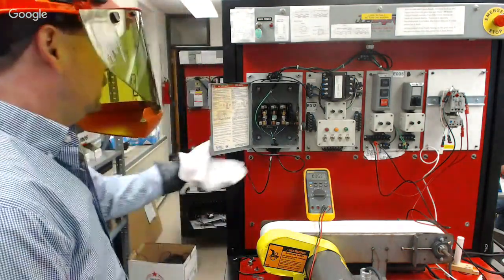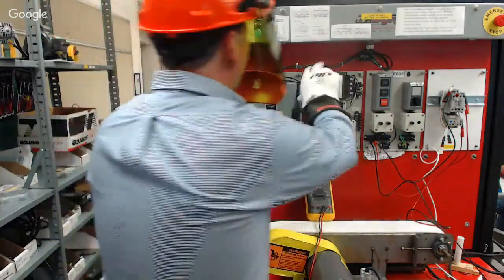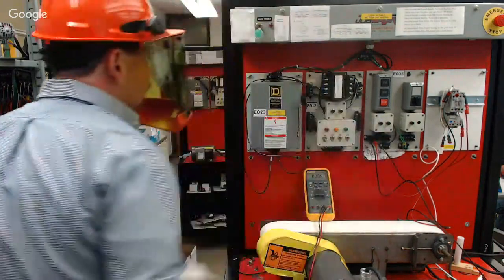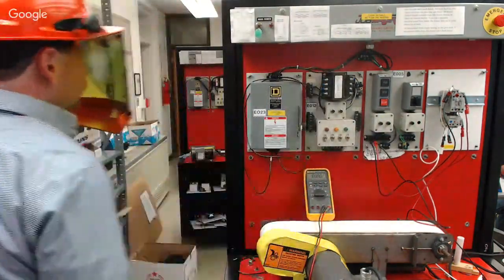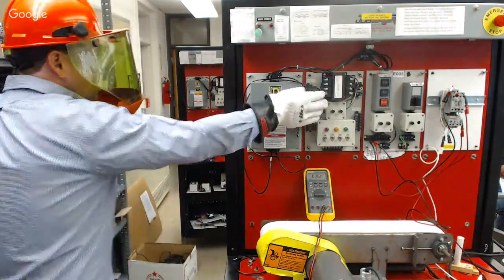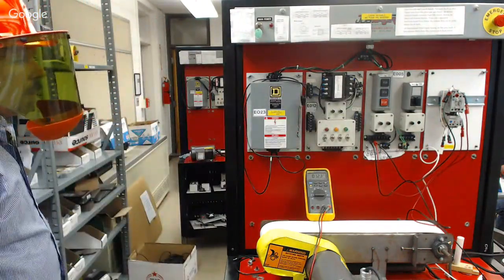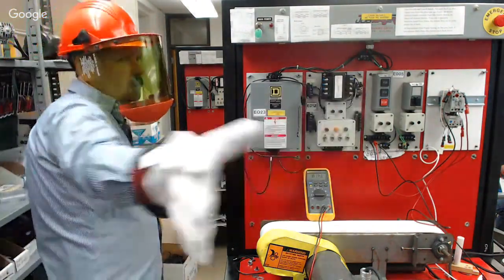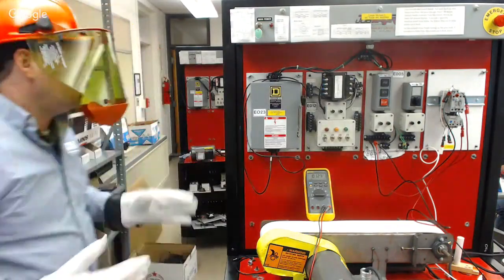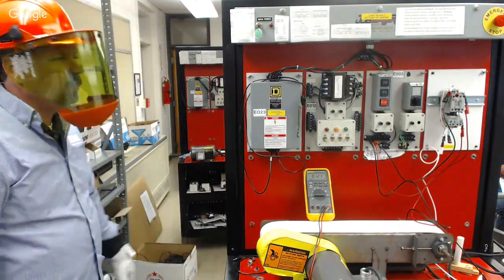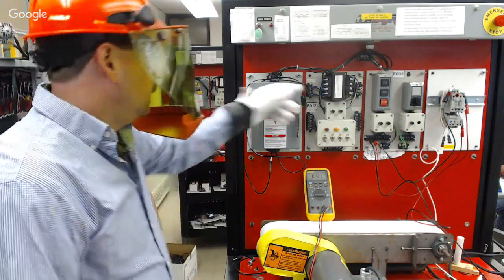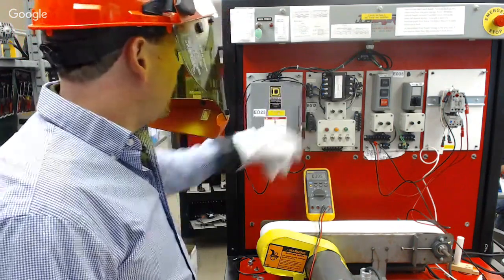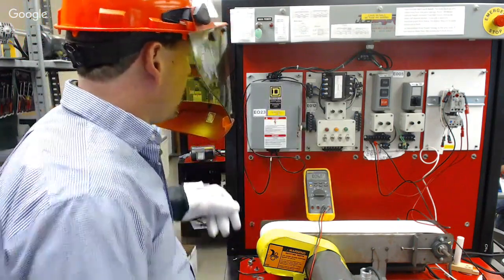So the new way, this is the proper way, is that when you get ready to energize this, you stand to the side and you turn it on. That way, if there is an arc flash when you power it up, it's going to blow out. You've got your gloves on and long sleeves, and you're not going to get hit. So I'm going to energize this, and we're going to do a cross check.